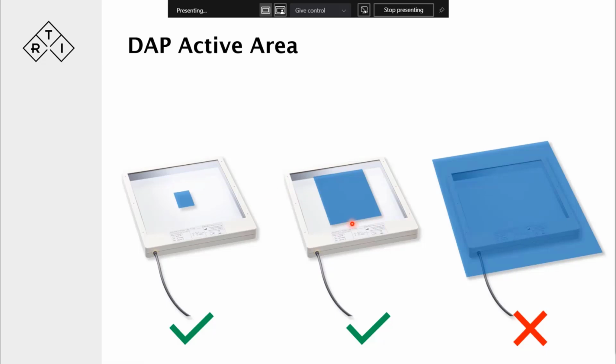If we look at these two examples, if we keep it close to a source, we'll get one DAP value. If we have the same settings, but increase the distance, the radiation situation would look like this. The beam would be slightly bigger at that point, but we'll have the same value for these two measurements if the settings are the same in the DAP area.